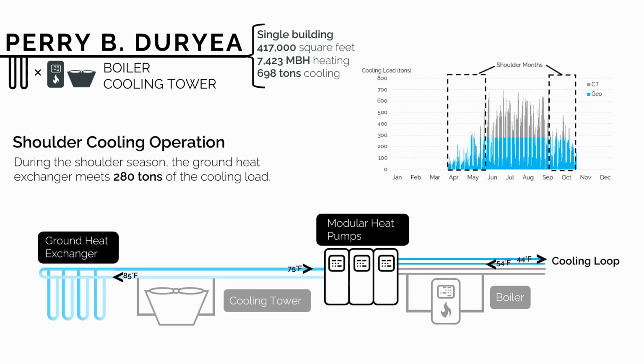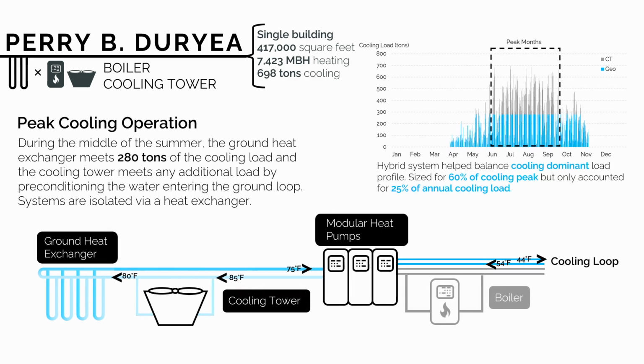During the shoulder seasons, that bore field, which was about 280 tons of capacity, will be able to handle all of that cooling load. So, springtime and fall, we're just running on the bore field. When we get to the peak load, the peak summer months, we are going to introduce the cooling tower into the loop. It's hydraulically separated with a heat exchanger, and that's going to precondition the water going to the ground, just so that we don't have any unintended consequences, temperatures in that ground loop.